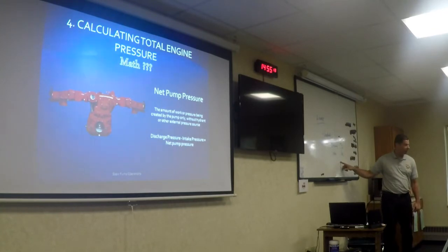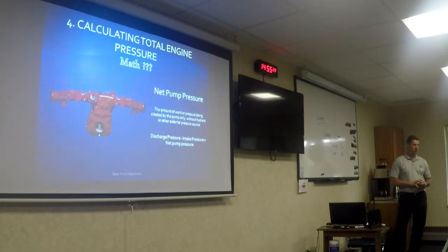What I'm saying is, you're telling us 20, but if you needed more water, Randy can actually give you a little bit more without going below the 10 residual. You're right, but you're risking cavitation and damaging the entire system and shutting the operation down.